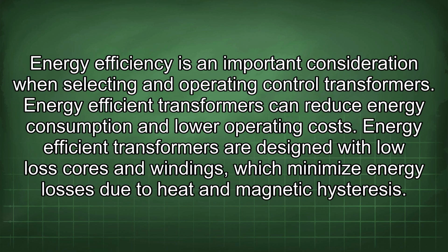Energy efficiency is an important consideration when selecting and operating control transformers. Energy-efficient transformers can reduce energy consumption and lower operating costs. Energy-efficient transformers are designed with low loss cores and windings, which minimize energy losses due to heat and magnetic hysteresis.